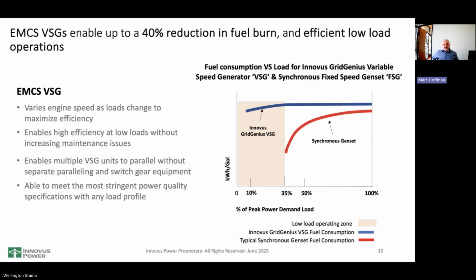You can see what happens with them, unfortunately, as you look at the x-axis on the chart on the right: as the demand for power on that generator drops from 100% to 50% down to 0, there's a linear degradation of efficiency, or saying it a different way, there's more proportionate fuel burn, and at some point it literally drops off a cliff, starting around 50, 60%. And the reason that's happening is that when you're forcing an engine, which is really an unnatural act for an engine, it wants to run at variable speed to stay efficient. Because it's forced to run at a single speed, it basically can only adjust for power.